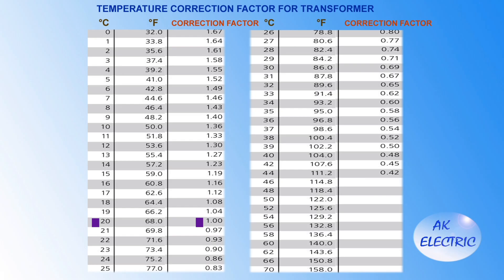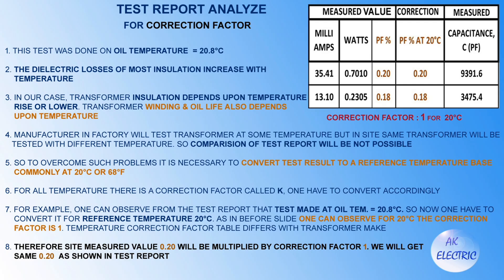The manufacturer in the factory will test the transformer at some temperature, but in the field the same transformer will be tested at a different temperature, making test report comparison difficult. To overcome this problem, it is necessary to convert test results to a reference temperature base, commonly 20 degrees Celsius or 68 degrees Fahrenheit. A transformer correction factor table is used for that purpose, and this table will differ according to transformer make, cold countries, and warm countries.